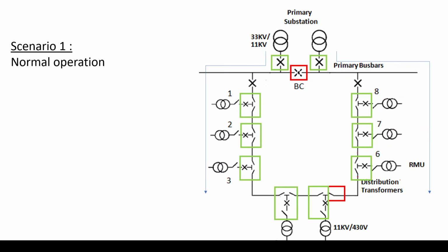So as you can see here, this is a typical ring, power distribution ring network. So I have here the primary substation, 33 over 11 kV transformers, for example. These are the downstream, these are the main breakers at the primary substation, and this is a bus coupler connecting these two sections from these two separate transformers.